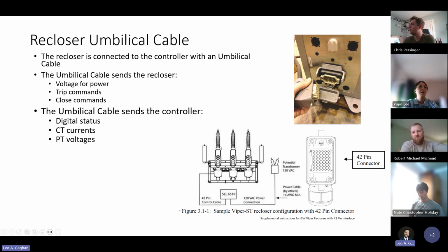You can see you've got your recloser. It's got that 42-pin control cable, which we can see right there. You can see where that plugs into the recloser. But it's not always a 42 pin. There's a bunch of different connectors you can buy, but that's a pretty typical one. And then up at the recloser, like we talked about, there's that voltage transformer, and that brings power to your recloser controller. Some of the typical things on that umbilical cord can bring digital statuses, open and close status, the CT currents, PT currents, trip commands, close commands. There are all sorts of different things that you can see on the wiring for that umbilical cord.